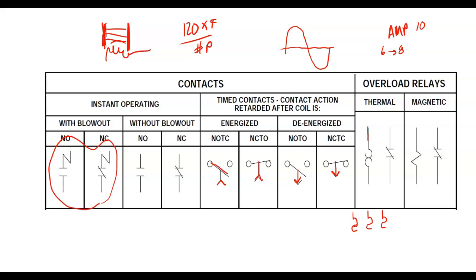So we need something that allows the motor to start, but if the motor stalls for a little while, it'll disconnect it. This is what these overloads are. These are overload sensors. So what we do is we have these overload sensors in each line, like this, and then the motor would be down here, off the screen. If your motor stalls, these would trip the actual relay. There would be an overload contact in the control circuit, and that would drop out the main control and kick the relay.